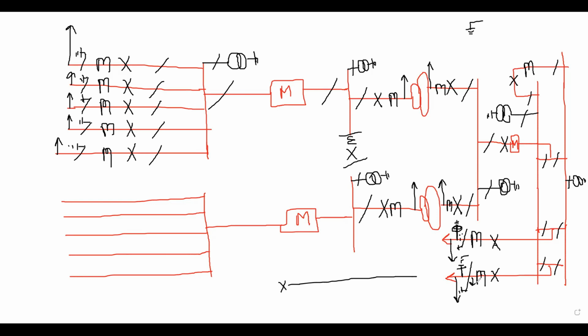Okay, a fault happened. If the CT is placed after the breaker, then how can the CT detect the fault? It cannot. And if you close the breaker in a fault condition, with a person standing and operating manually, it will damage the nearby equipment. In the distance protection scheme, we call this an end fault.